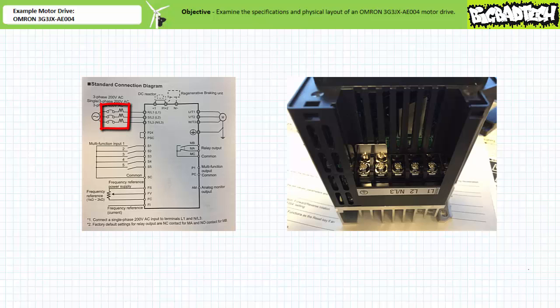Additionally, note the standard connection diagram indicates a circuit breaker must be installed between the power supply and the motor drive for disconnection purposes. Note this motor drive necessitates no additional power connection to power the device itself. This motor drive is powered using the primary L1 to L3 connections.